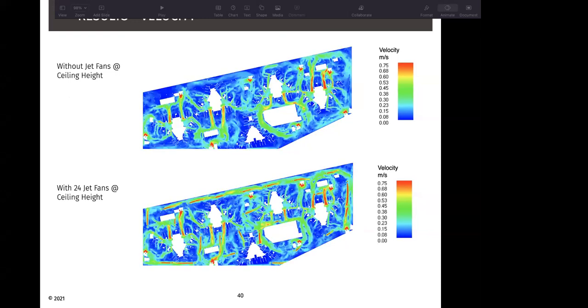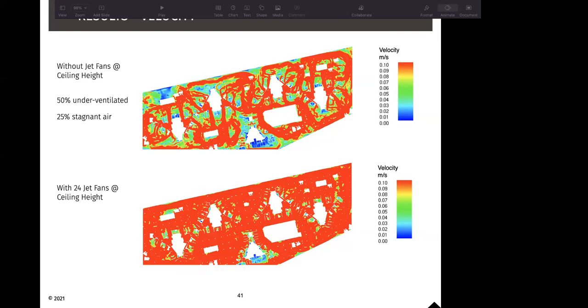Now, looking at the velocity contours at the jet fan height, you can see that there are portions which are blue, which indicate underventilated stagnant zones. And considering the same, the jet fans have been placed in the car park to move the air in the flow of the natural fresh air path, and to optimize that, to basically get rid of all the blue and the green portions in the car park. So again, looking at the velocity scale at 0.1 meters per second, we can see that the jet fans have now reduced that underventilated stagnant zones in the car park.